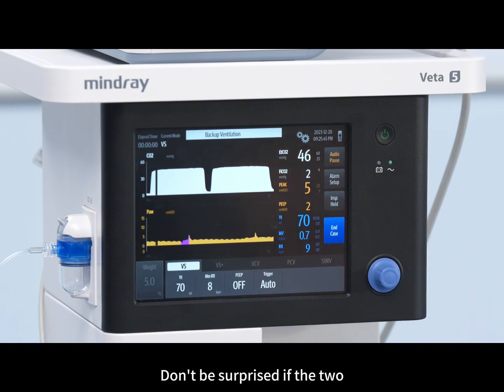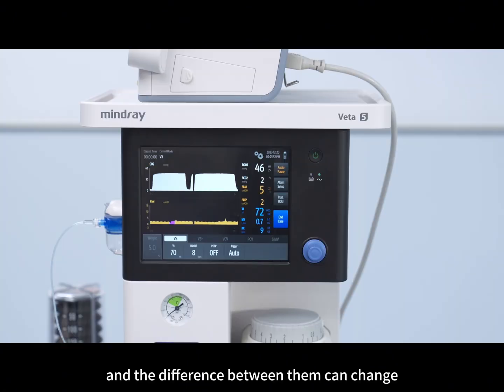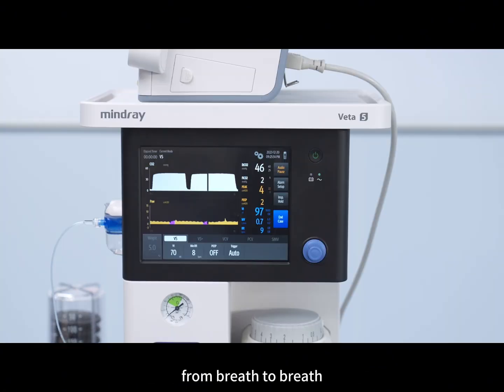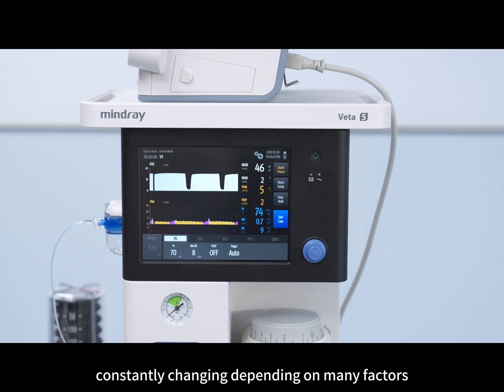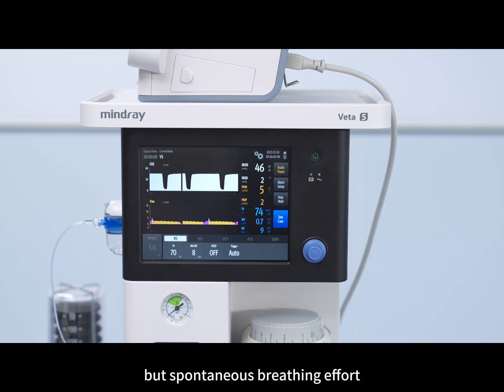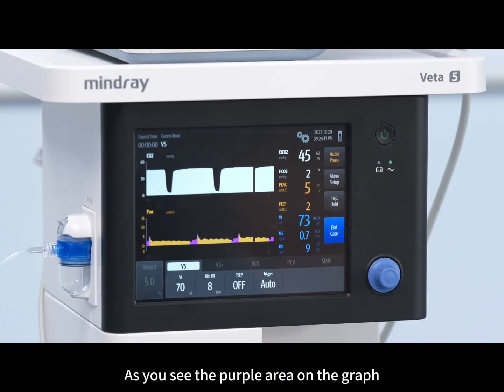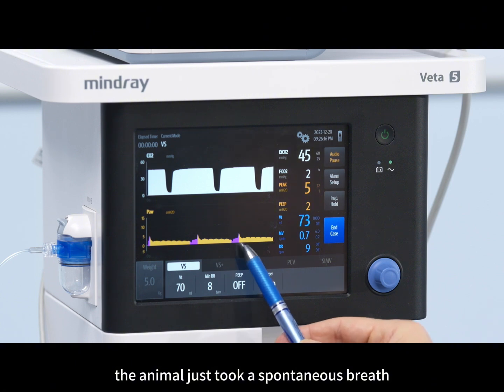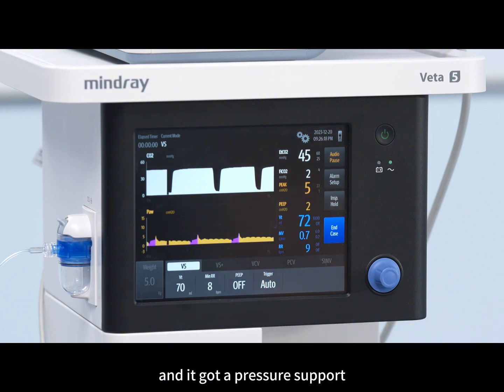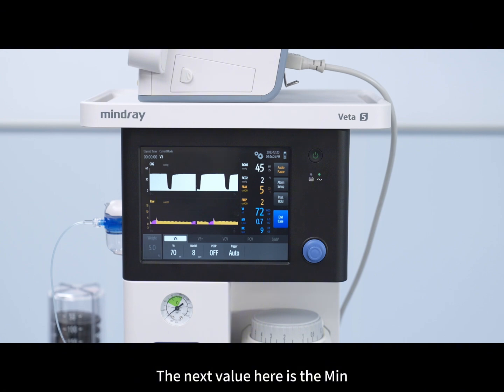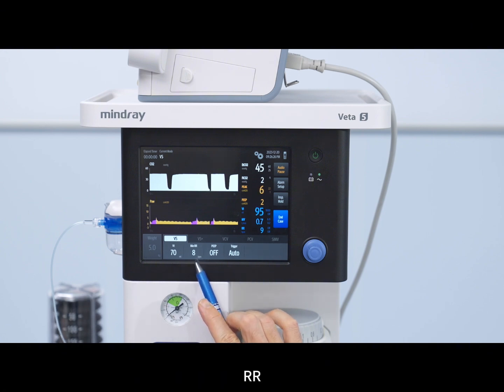Don't be surprised if the two do not match completely, and the difference between them can change from breath to breath. This is normal because the chest compliance of the animal is constantly changing depending on many factors, but spontaneous breathing effort will have a large influence on it. As you see the purple area on the graph, the animal just took a spontaneous breath and it got a pressure support. The next value here is the minimum respiratory rate.